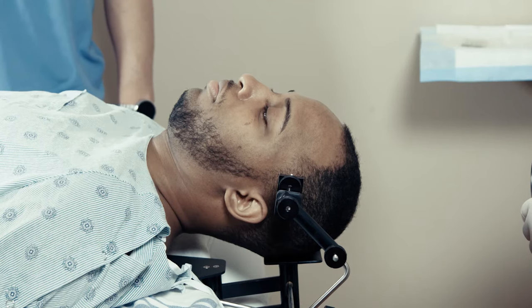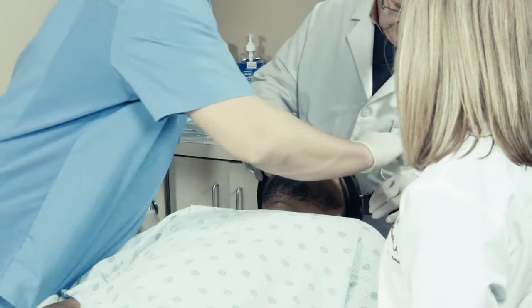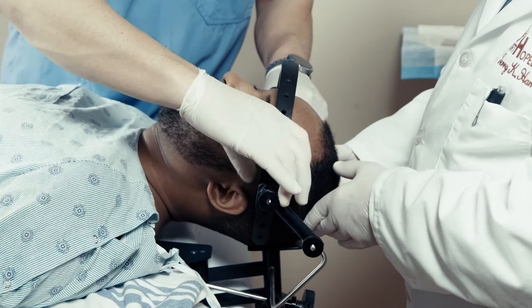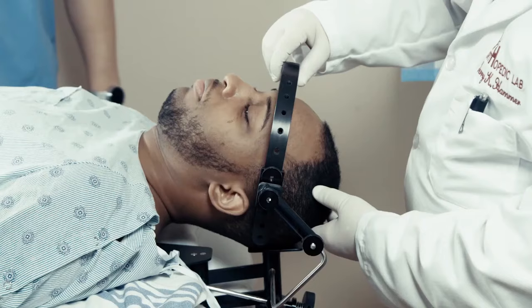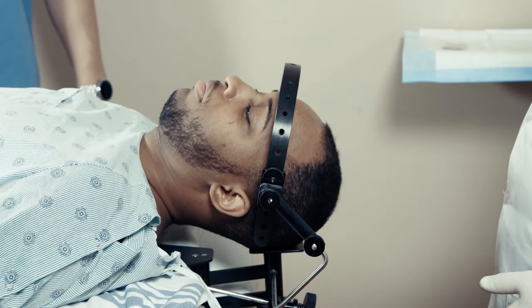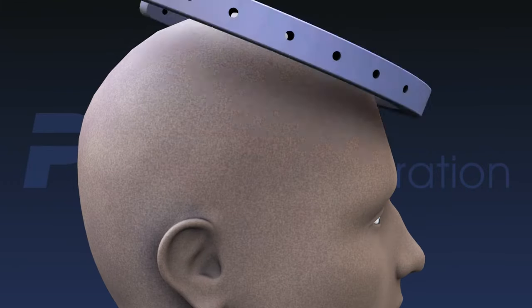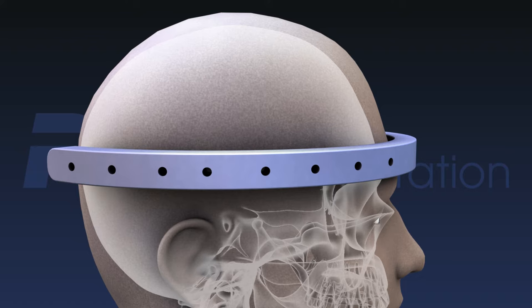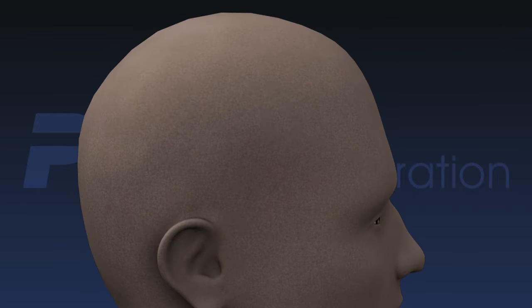Several methods of positioning the ring during its fixation to the skull are available to the physician. PMT provides an outrigger which connects to the headholder. The skate assembly allows motion in all three planes and provides the most rigid positioning of the ring. Optimal ring positioning is symmetrically around the skull, below its greatest diameter. The ring should be free of the top of the ear. Additionally, ring position dictates pin position.